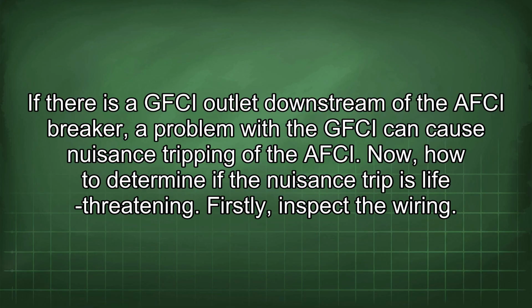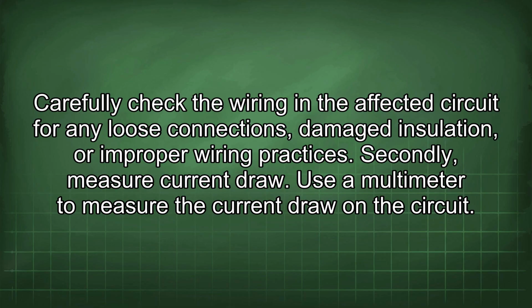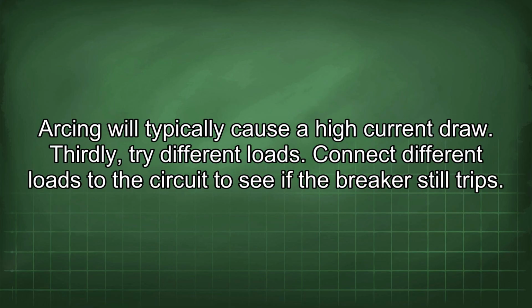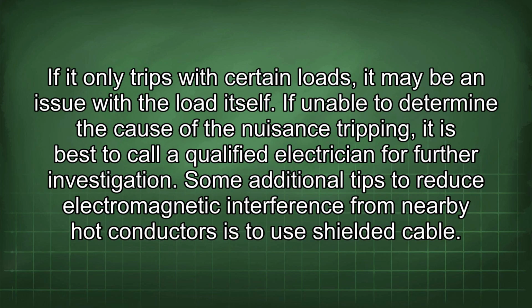Firstly, inspect the wiring. Carefully check the wiring in the affected circuit for any loose connections, damaged insulation, or improper wiring practices. Secondly, measure current draw. Use a multimeter to measure the current draw in the circuit. Arcing will typically cause a high current draw. Thirdly, try different loads. Connect different loads to the circuit to see if the breaker still trips. If it only trips with certain loads, it may be an issue with the load itself. If unable to determine the cause of the nuisance tripping, it is best to call a qualified electrician for further investigation.